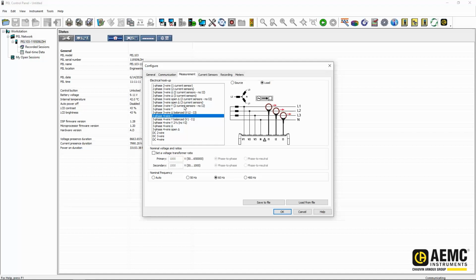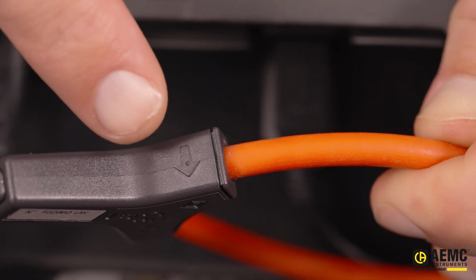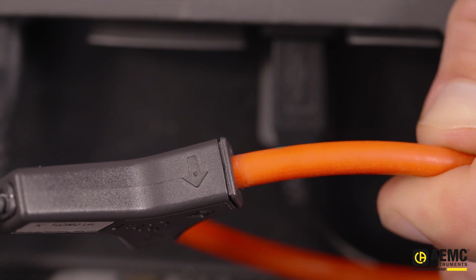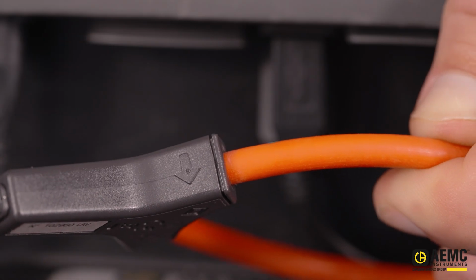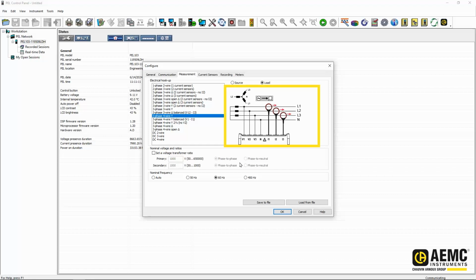The Measurement tab allows us to select the correct electrical hookup for our monitoring project. Here we've selected 3-phase 4-wire Y. I can see the correct orientation of my sensors and how they should be installed on my panel. Make sure that you can install your sensors with the arrow pointed towards the load, as pictured in the diagram on the screen. I can also configure voltage transformer ratios below the electrical hookup selection.